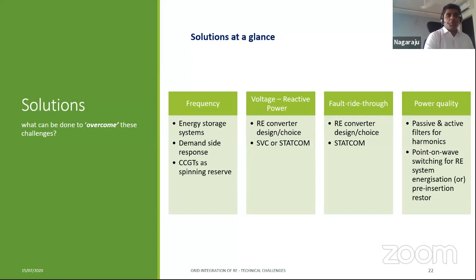Some of the solutions we provide for these problems is point-on wave switching. That is to choose at what point on the AC waveform the circuit breakers need to be closed onto the grid to energize the system. There is a lot of technical background on this. For example, if you're closing the breakers when the voltage is at 0 on that particular phase, you will see a lot of current drawn by the wind turbines, wind farms, that will create huge voltage drops. But if you choose cleverly to close the breakers at a different point, somewhere close to the peak, the currents will be low and hence the voltage dip will be low.